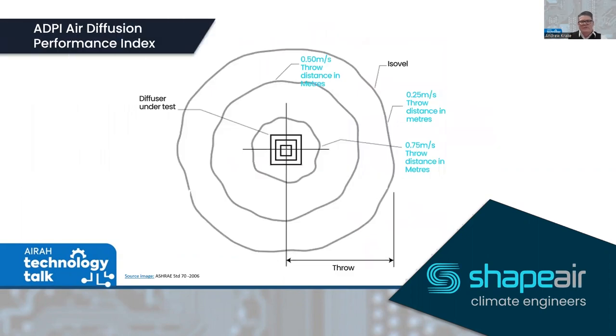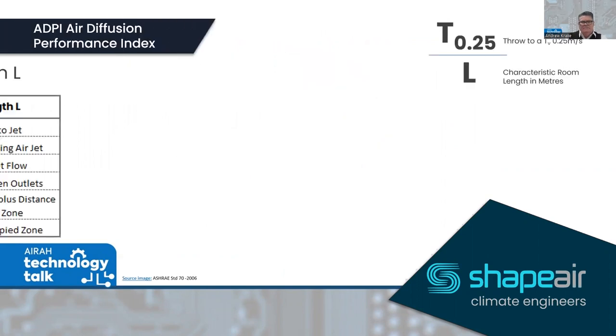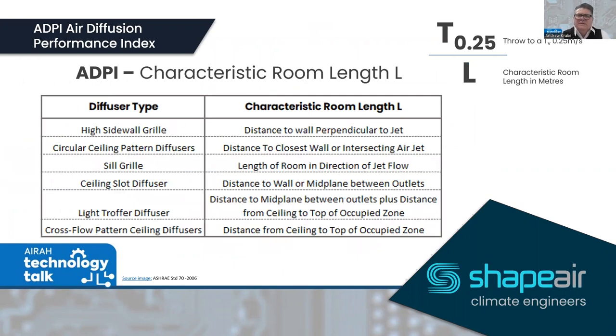For a radial outlet, measurement is done on a radial basis. Remember the formula: T to 0.25 m/s as a throw value divided by L (the characteristic room length). The characteristic room lengths include: for sidewall registers the distance to the wall perpendicular to the jet; for circular or radial diffusers the distance to the closest wall or intersecting jet; and values for sill, slot, light air troffers, and cross-flow pattern diffusers.